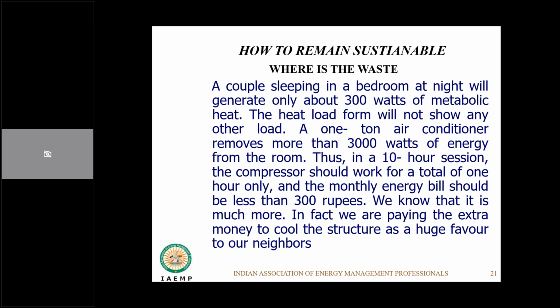A person's metabolic energy heat will not be more than 300 watts. So if there are two people in the room, it's under 600 watts. If I'm putting in around 1 ton of air conditioner, which is almost around 3,400 watts, and it is removing such a high amount of energy from the room, where the heat input is only 600 watts, we would imagine that this air conditioning system has to hardly run.